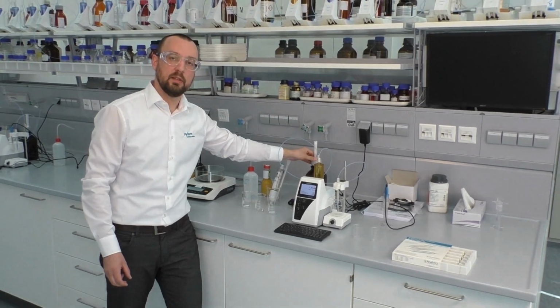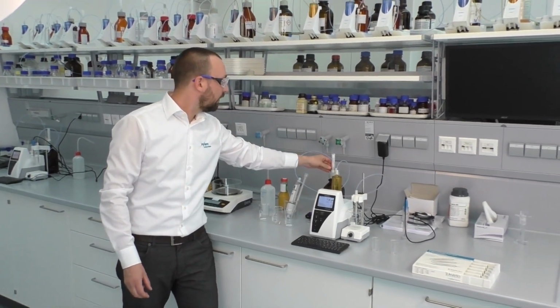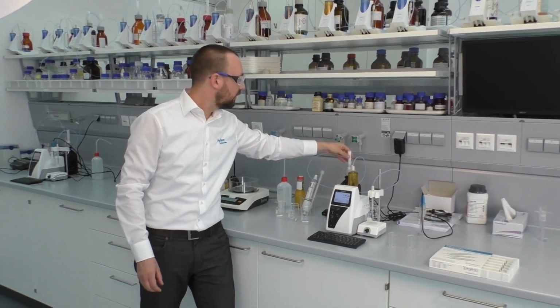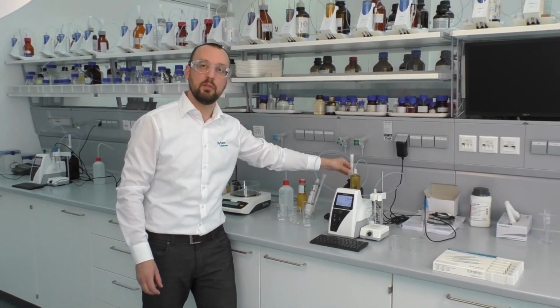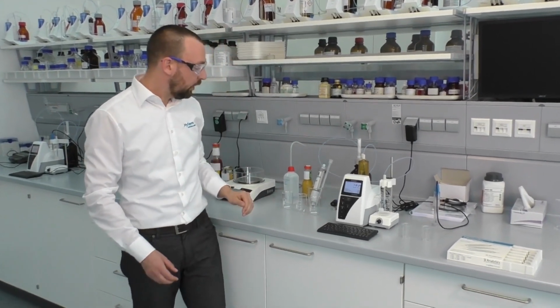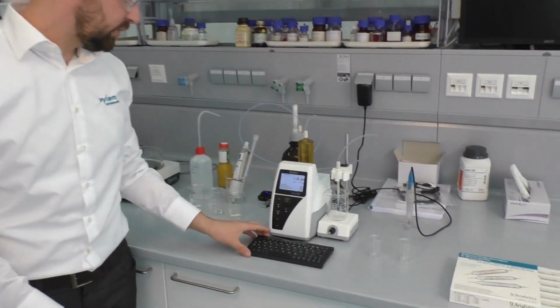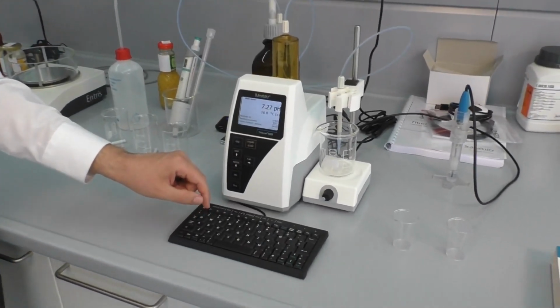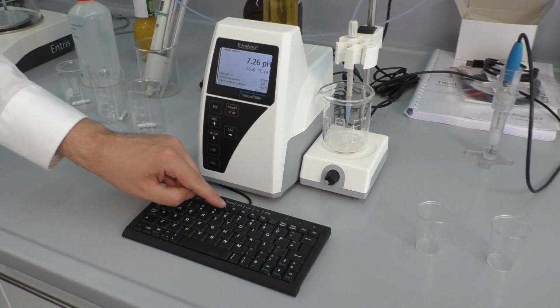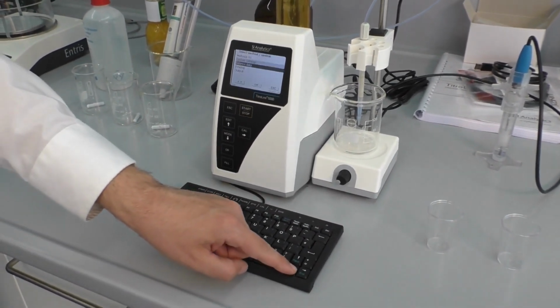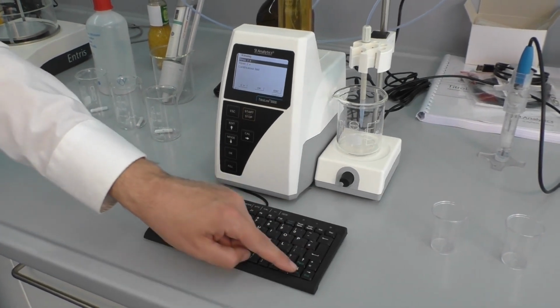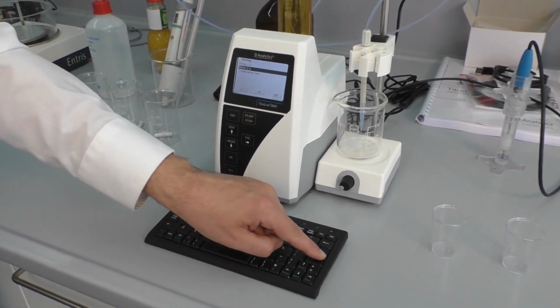After the installation is completed, the burette needs to be filled with the titration reagent. In our example, we want to titrate the total acidity in juices, therefore we need sodium hydroxide as titration reagent. Because of the sodium hydroxide, we need soda lime as protection against CO2 from the ambient. To fill the burette with the titration reagent, we use the rinsing mode of the titrator. Therefore we press F6 on the keyboard, go to rinsing, and then we start the rinsing 2 times.